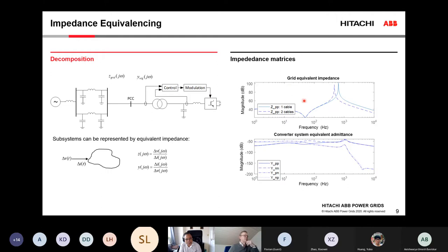So for the grid side, we can see the impedance calculated, the positive sequence impedance. Normally in these types of studies, we assume we have symmetrical systems, so we only need to look at the positive sequence. But there is a clear resonance at this point that would shift a little bit depending on whether I have one or two cables in operation.